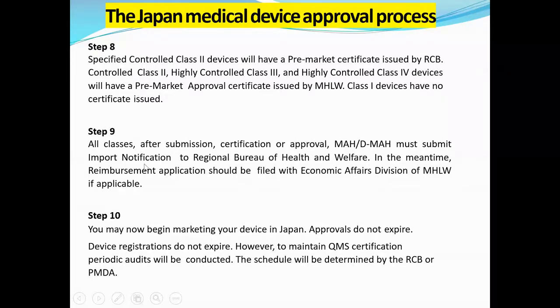So for all classes, after submission, certification or approval, the MAH or agent must submit an import notification to the Regional Bureau of Health and Welfare. In the meantime, a reimbursement application should be filed with the Economic Affairs Division of MHLW if applicable. Then you may now begin marketing your device in Japan. Approvals do not expire. The device registration does not expire. However, to maintain quality management system certification, periodic audits will be conducted. The schedule will be determined by the RCB or PMDA.